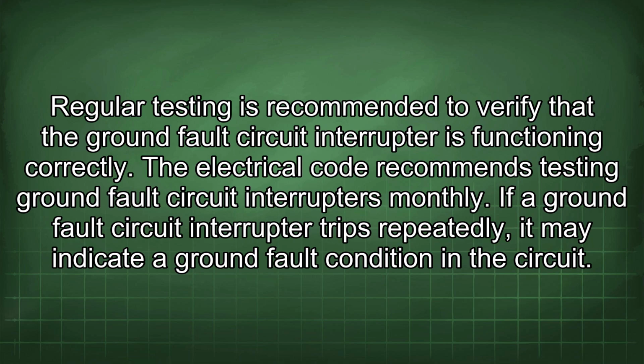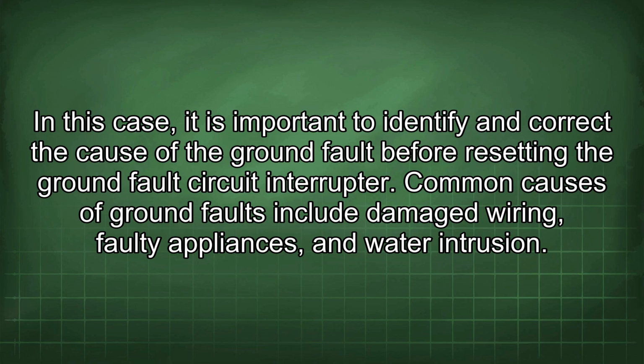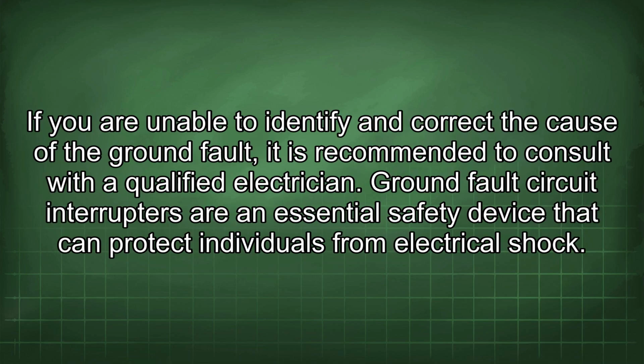If a ground fault circuit interrupter trips repeatedly, it may indicate a ground fault condition in the circuit. In this case, it is important to identify and correct the cause of the ground fault before resetting the ground fault circuit interrupter. Common causes of ground faults include damaged wiring, faulty appliances, and water intrusion. If you are unable to identify and correct the cause of the ground fault, it is recommended to consult with a qualified electrician.